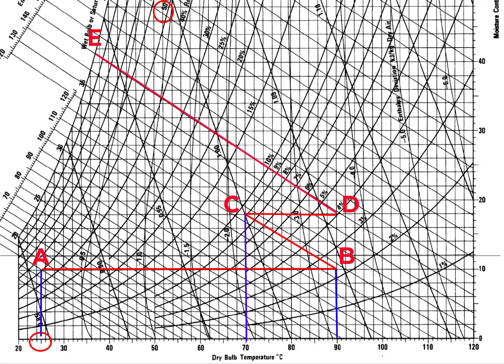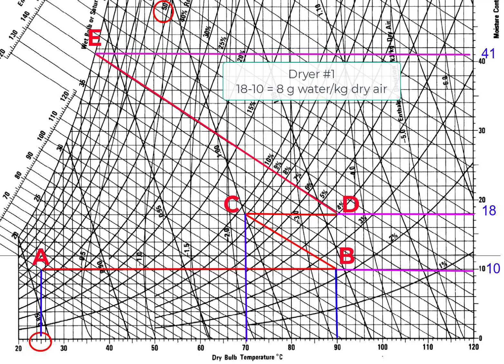Now we can read the values of moisture content or humidity ratios at various locations. For point E the humidity ratio is 41 grams of water per kilogram of dry air. For location D the humidity ratio is 18 grams of water per kilogram of dry air. For location B the humidity ratio is 10 grams of water per kilogram of dry air.